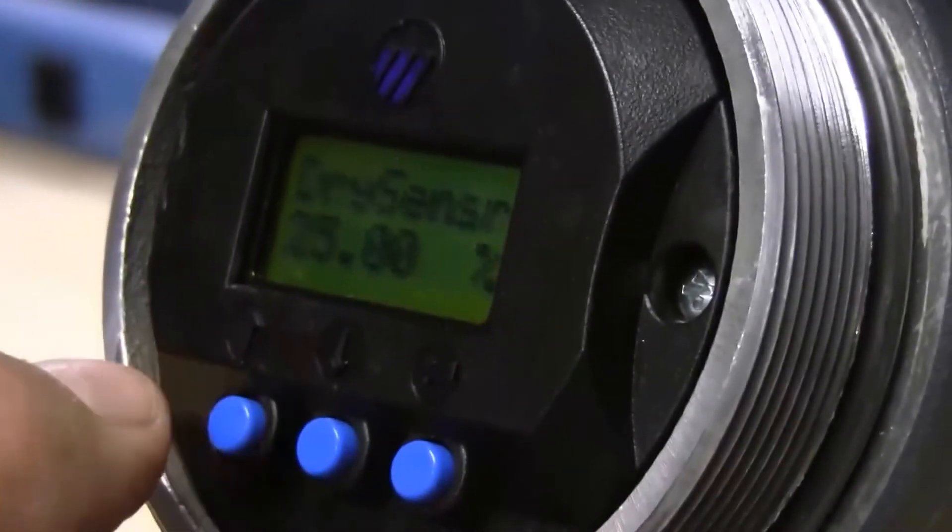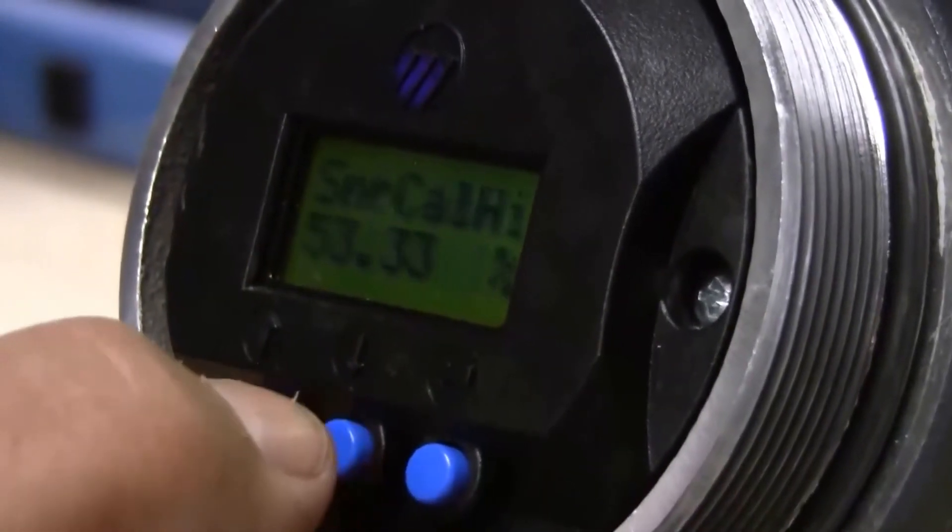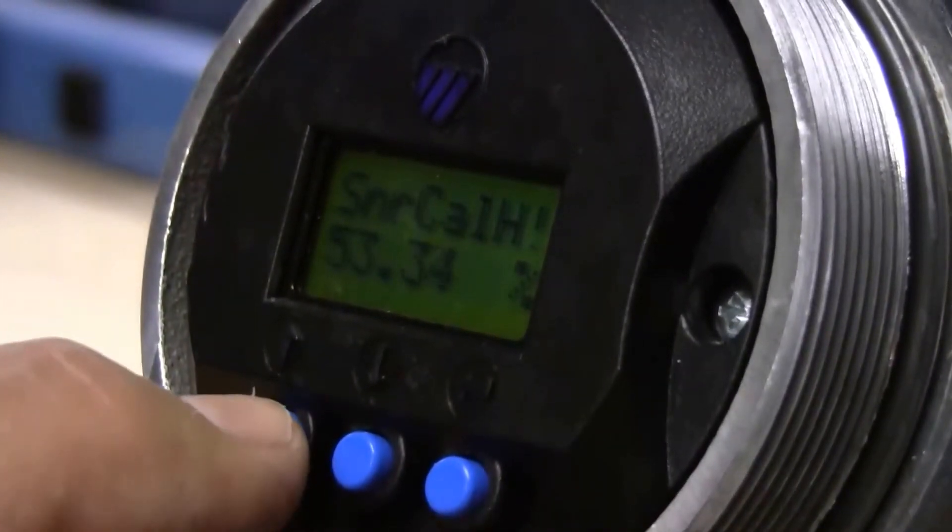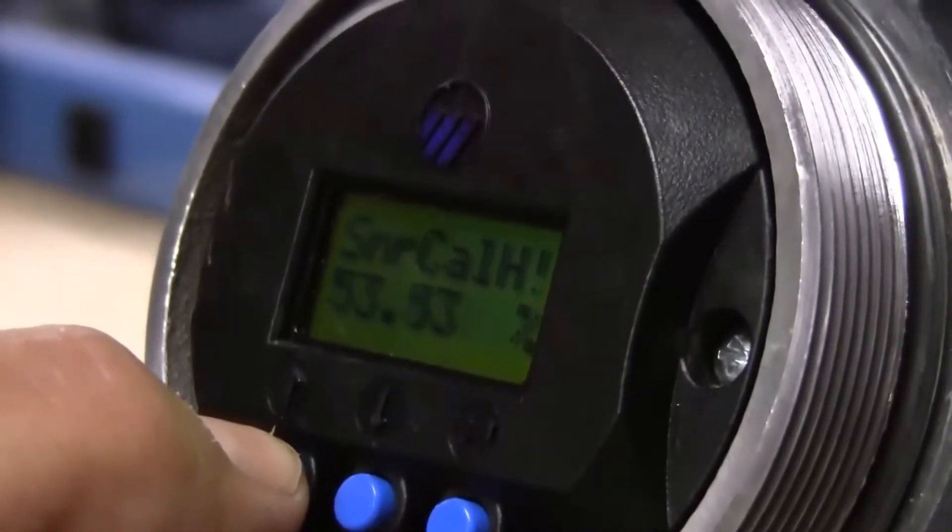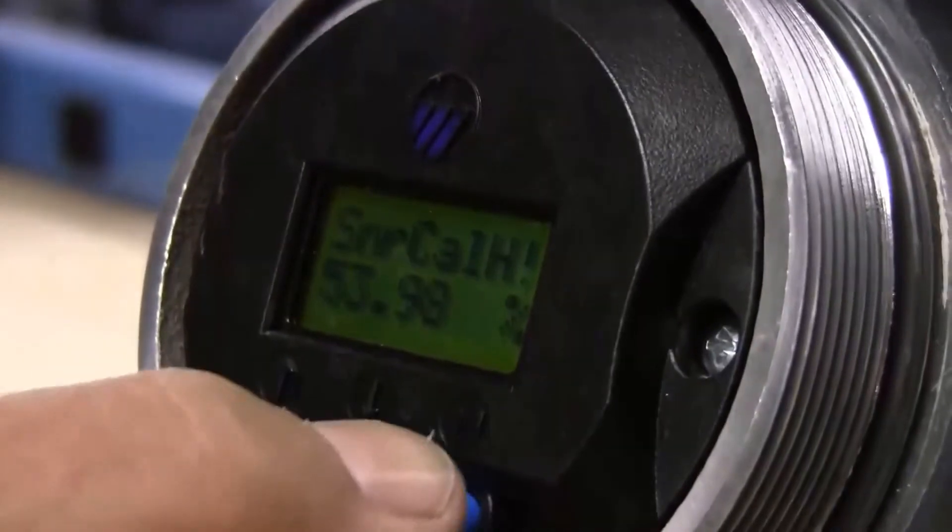So sensor cal high, go back to our LVDT and that's 53.98. So we're going to enter that into the sensor cal high. Enter and up arrow to 98, 53.98. Enter that.